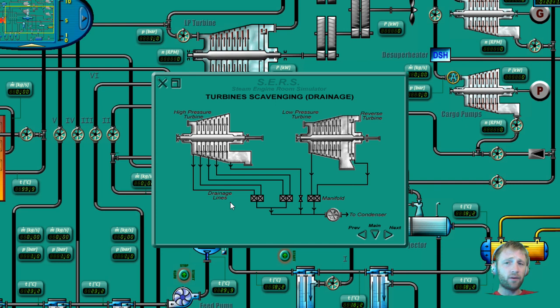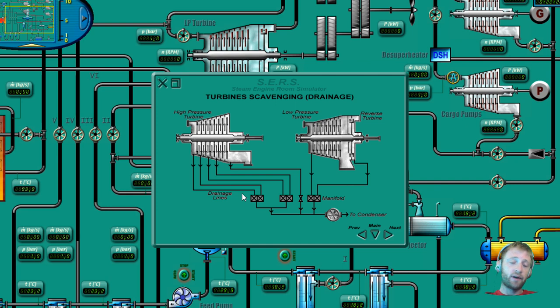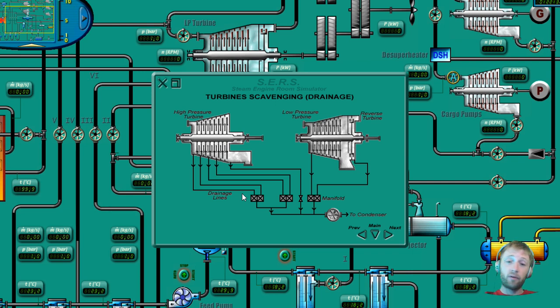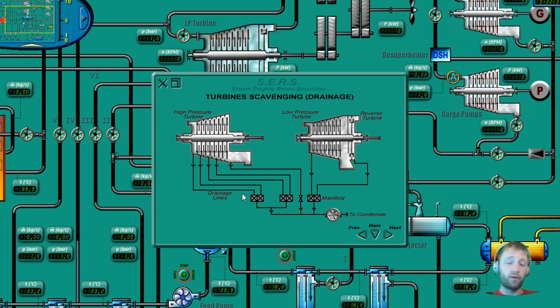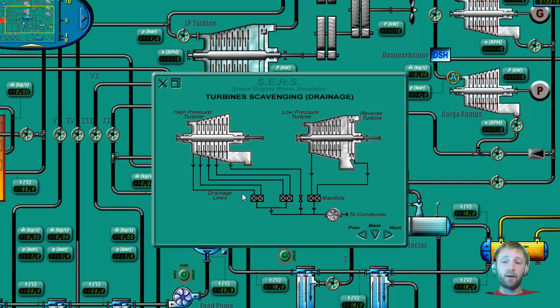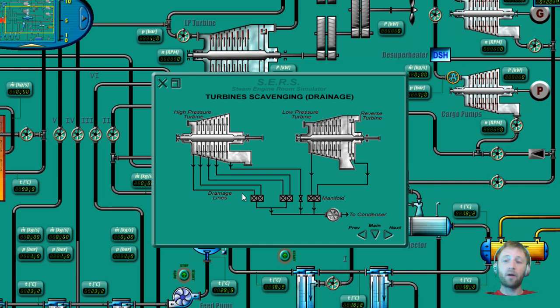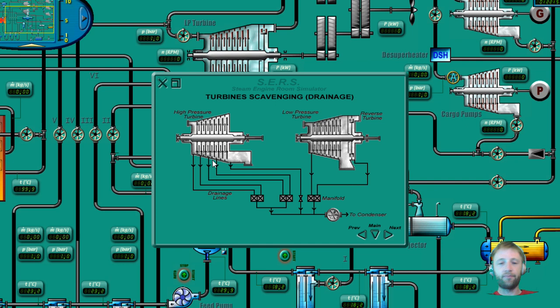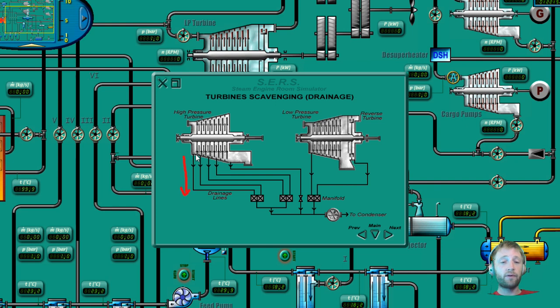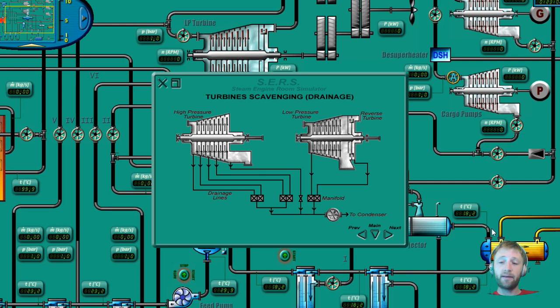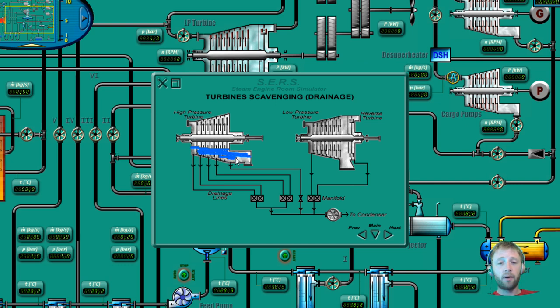In all systems is almost the same thing, because the media that we use, in one case steam, also can be compressed. And also freon can be compressed. All these gases and liquids have their properties, but they're compressible on some point. As we know, liquids are not compressible and it's also really dangerous. So that's why we need a proper drainage here. We try to avoid any water and condensation to be stuck here, for the reason if we have accumulation of water here, our blades will be broken.